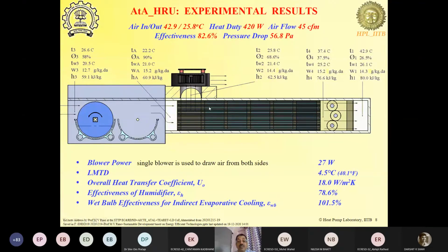These were the units where we use plastic air-to-air heat exchangers to cool air from 42.9 degrees centigrade and 26.5% RH down to 25.8 degrees centigrade. Okay, the humidity, of course, is maintained, and so the RH goes up when the temperature is reduced. And this was possible using the exhaust air from the conditioned space.